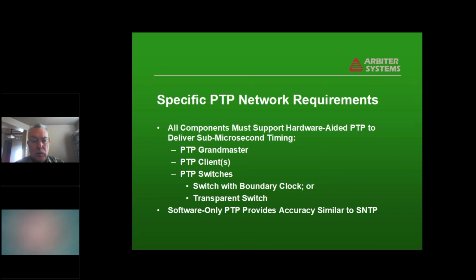It is possible to have a subsection of the network that doesn't have hardware aided PTP ports if it's serving less critical applications, like applications that are just doing recording at the 1 millisecond level and you don't need the hardware aided sub-microsecond timing. But that requires careful design by somebody who really knows what they're doing. So it's one of the reasons people still like IRIG, actually, is because it just goes from one point to another and there's nothing in there to get involved in it. You never have unsolicited broadcast traffic or anything like that on an IRIG signal.